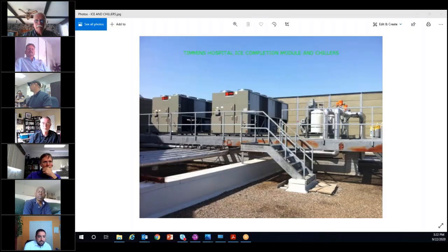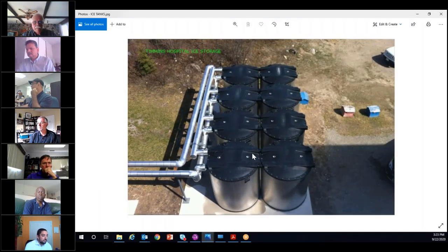So the design that the Trane team with the hospital and the local consultant came up with was really hinged around thermal energy storage or ice storage being added into the system that was there already. So what ended up happening is the 4 chillers that were there before ended up being retrofitted to 2 chillers of a similar size and 8 thermal energy storage tanks or ice tanks. So this was just a picture coming off the roof of the 8 ice tanks that ended up going in there.